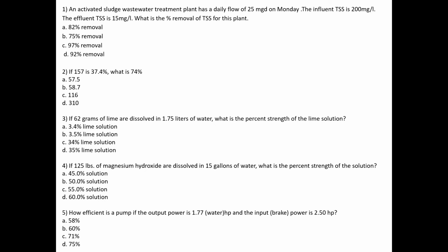It's a rounded number, but essentially it's 33,000 foot-pounds per minute, which is 1 horsepower, divided by 8.34 pounds per gallon, the weight of water. That's where they get 3,960. On a calculator it's actually 3,956. I don't know why it's rounded up, but that's the standard formula: GPM times TDH over 3,960.